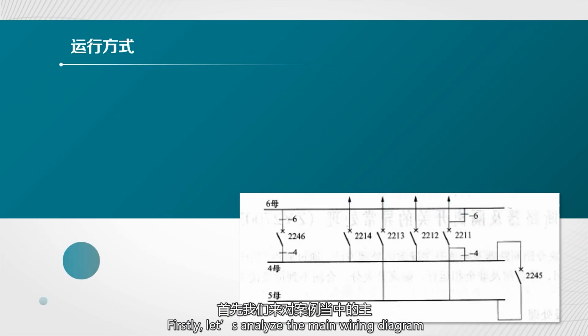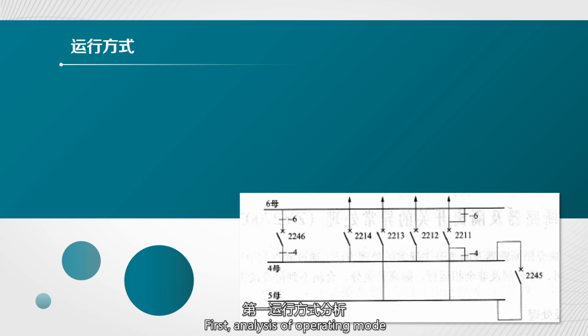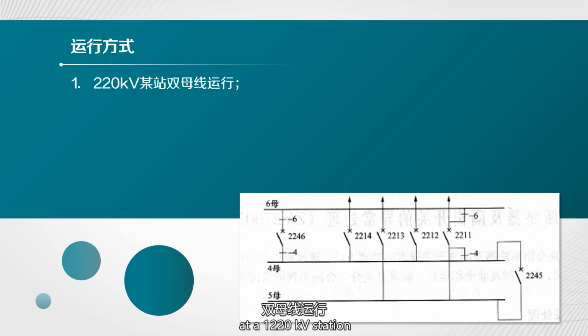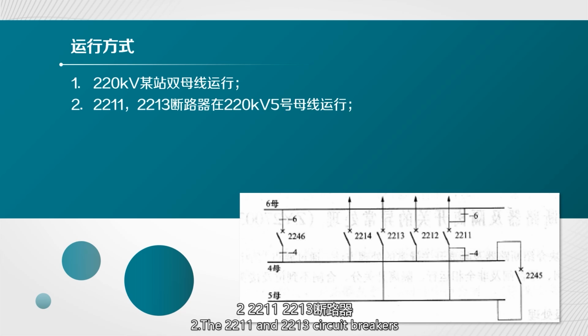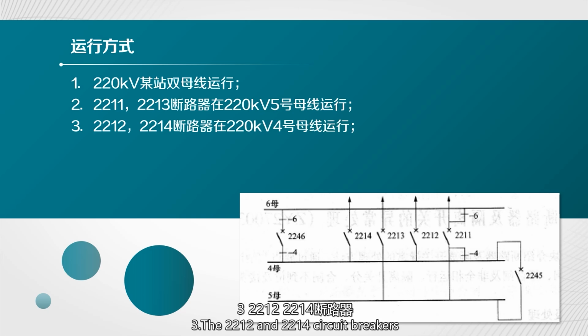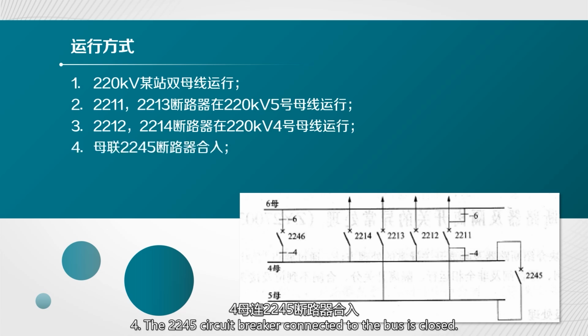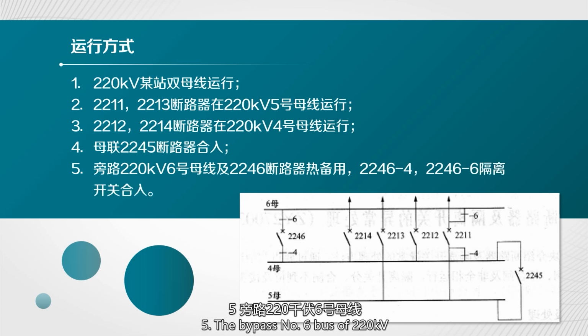Firstly, let's analyze the main wiring diagram in the case study. First, an analysis of operating mode. First, dual bus operation at a 220 kV station. Second, the 2211 and 2213 circuit breakers operate on the number 5 bus of 220 kV. Third, the 2212 and the 2214 circuit breakers operate on the number 4 bus of 220 kV. Fourth, the 2245 circuit breaker connected to the bus is closed.